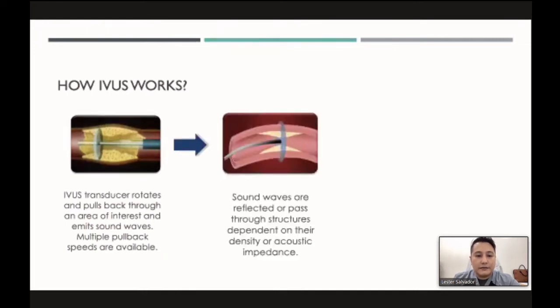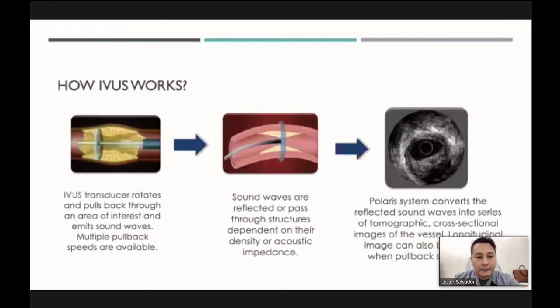The density of the structure that the ultrasound is in contact with will determine whether the sound will be reflected or pass through the structure. This is referred to as acoustic impedance. After that, the reflected ultrasound returns to the transducer and is converted into an electronic image. The transducer spins at high speeds within the vessel while pulling back in the catheter, and it takes pictures in 360 degrees.